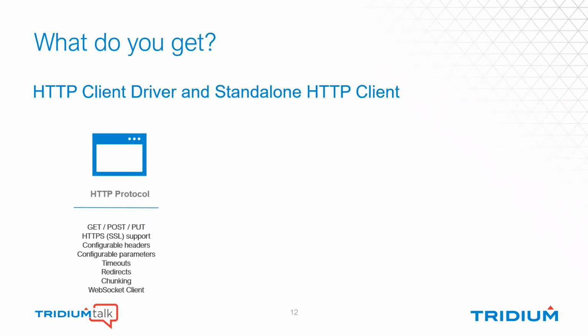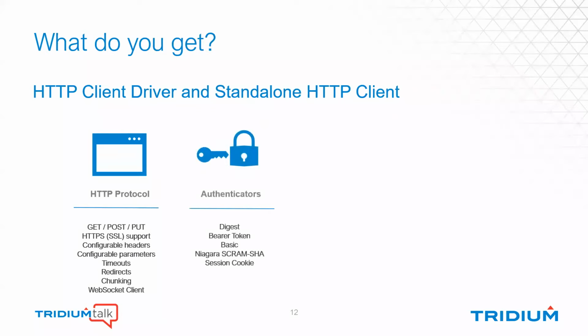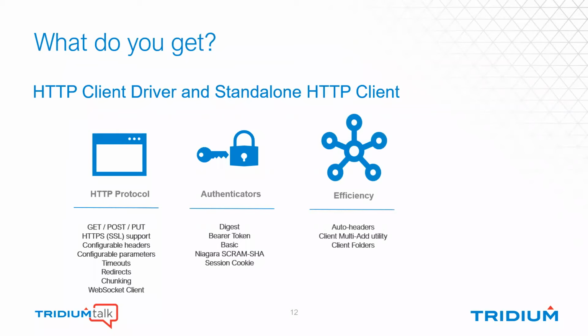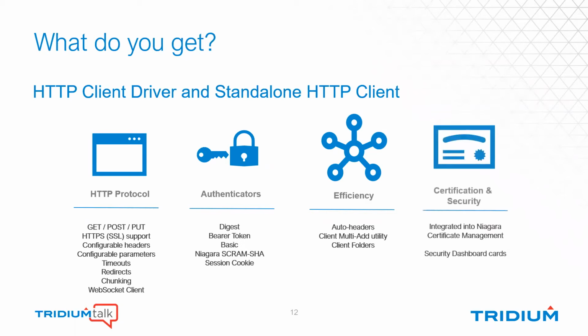You do get HTTPS support, so that's why we call it HTTP client driver. It does cover the secure socket layer as well. We have configurable headers, configurable parameters, and all those tools: timeouts, redirects, etc. We use a number of standard authenticators as well. And we built in some tools like auto headers, client multi-add utilities, and client folders to help with efficiency. And of course, it's integrated into Niagara certificate management for security and can feed through, so we have security dashboard cards showing up too.